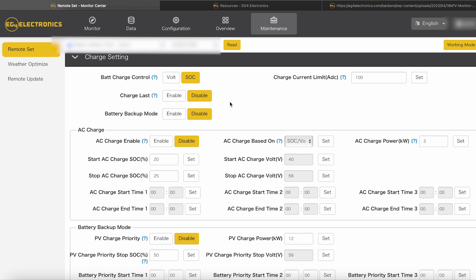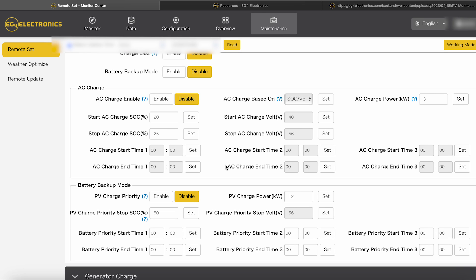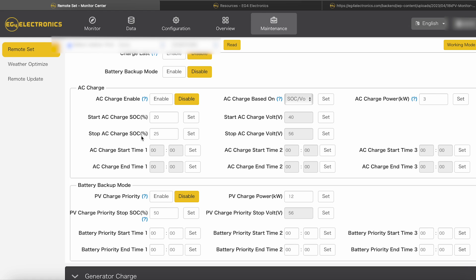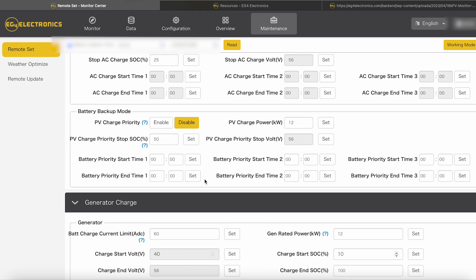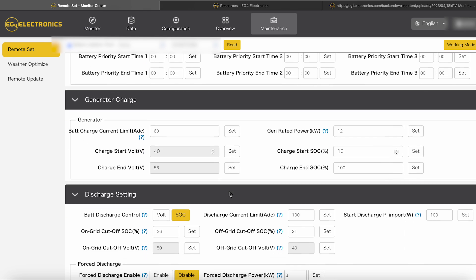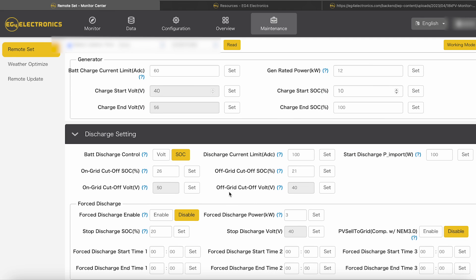Then the charge settings. I got it set like I was talking about. I got it set the state of charge because I got battery communications. Charge last is disabled. And battery backup mode is disabled. AC charge, you can enable or disable that just depending on what you want to do. So right now this is saying disable, but I know I got this enabled. So I'm not sure if I changed that by accident. But basically, if it gets down to 20%, as you can see, I got it set. It'll start AC charging and it'll go up to 25% because I also don't want to get battery to get super low. So I'm guessing I'm going to have to enable this back. Somehow I must have disabled it.